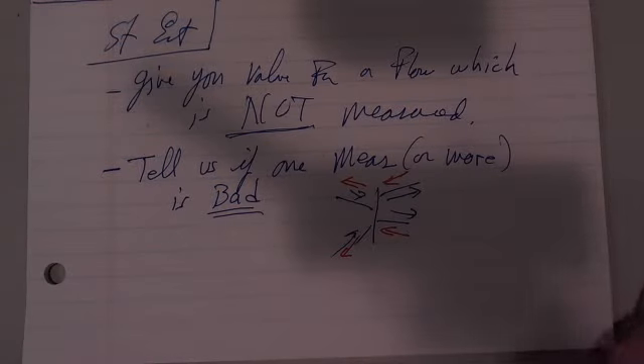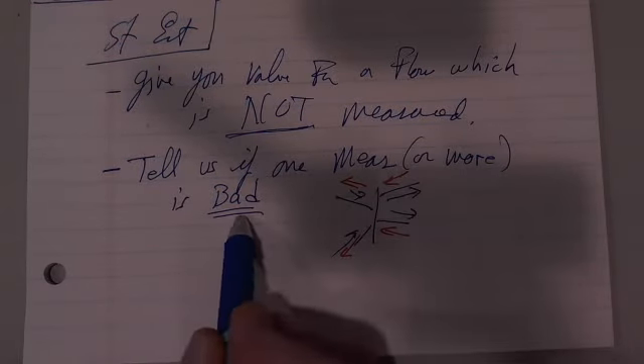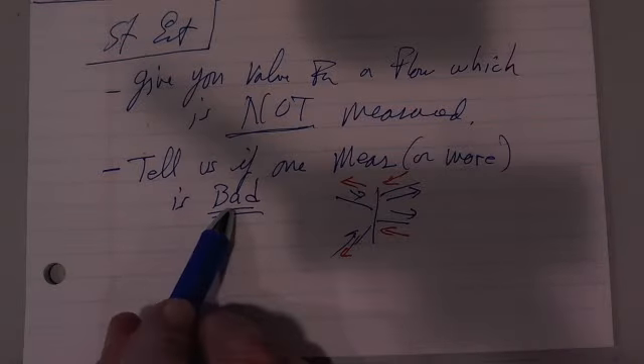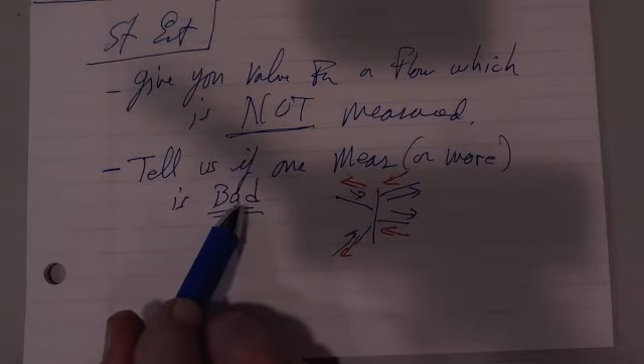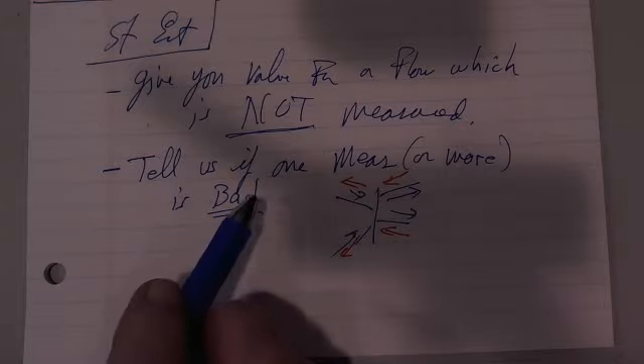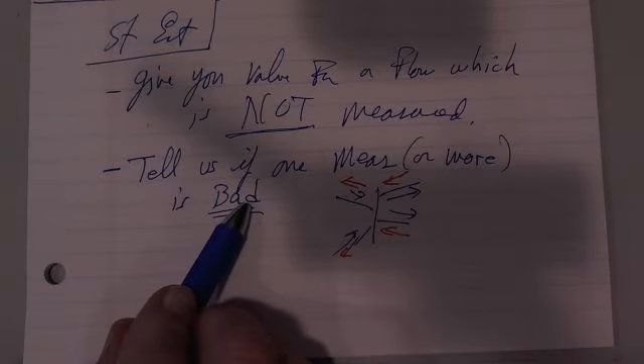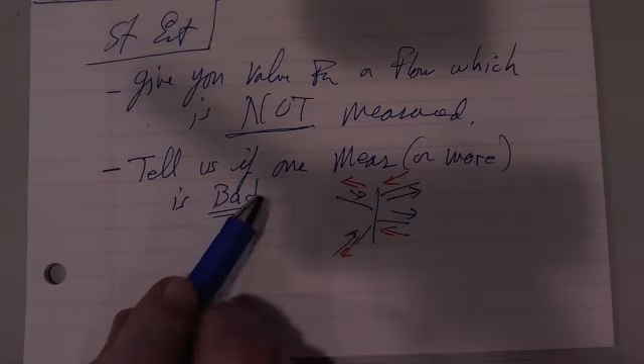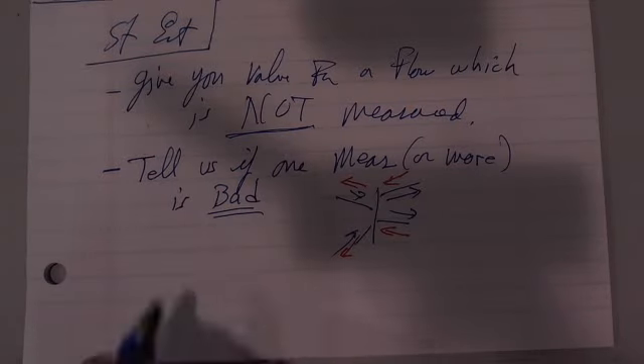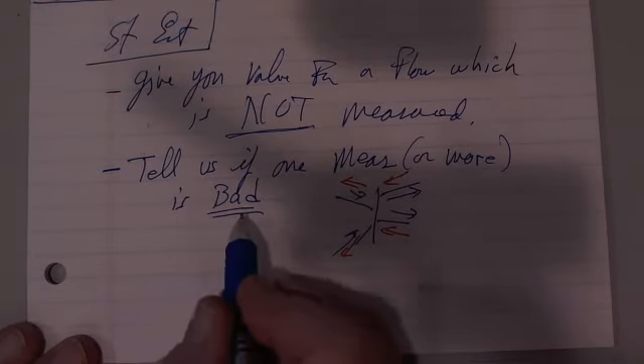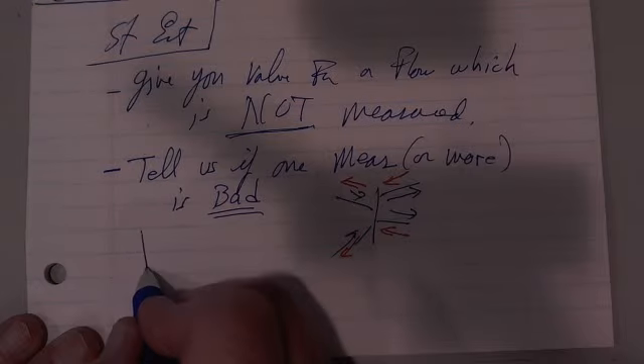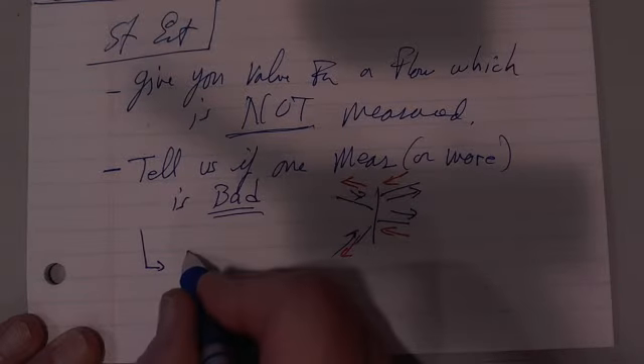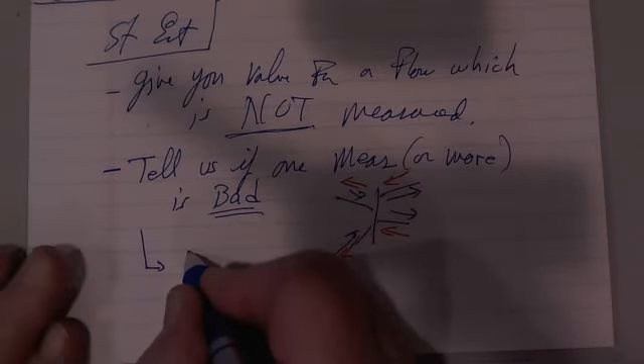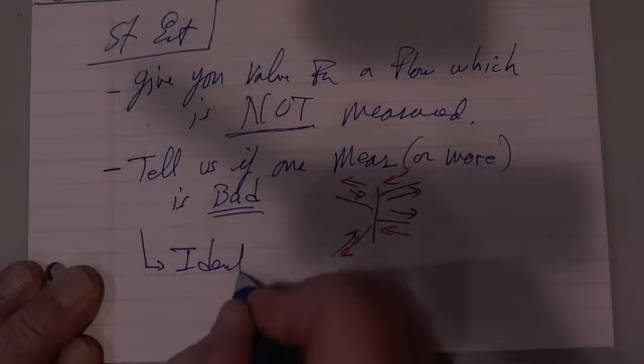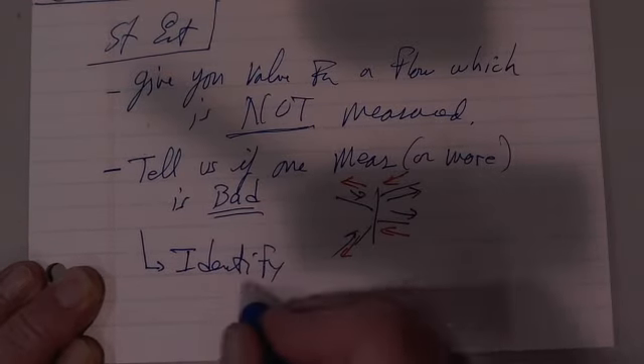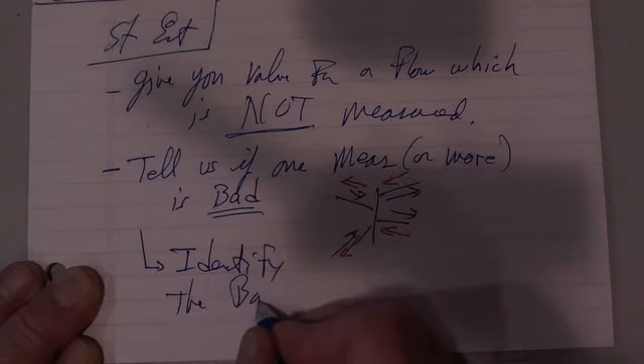That's a bad measurement, or it sometimes simply means the transducer itself, or the electronics, the magnetic circuits, whatever, goes bad. The state estimator can tell you if there is a bad one, and hopefully it can actually identify the bad measurement.